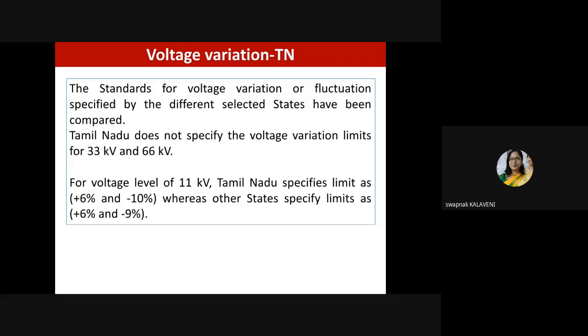Say, for example, the standards for voltage variation or fluctuation specified by the different selected states have been compared. For a voltage level of 11 kV, Tamil Nadu specifies the limit as plus 6% to minus 10%. Suppose I am delivering power at 11 kV, the maximum voltage variation allowed is plus 6%. On the minus side, minus 10% is permitted. The utility can deliver power at a voltage level of 11 kV with a variation of plus 6% or minus 10%.